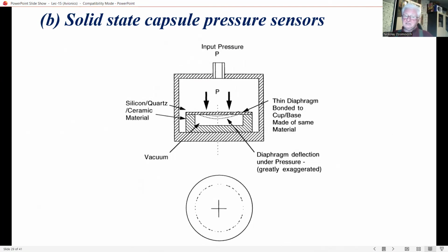Semiconductor technology is used in the fabrication of these sensors and, together with the absence of moving parts, has led to the description as solid state. The technology also enables very small sensors to be fabricated with excellent repeatability because of the semiconductor processes used. The deflection of the solid-state capsule under pressure is typically only 25 up to 50 micrometers for full scale, or even less. The techniques which have been adopted to measure this very small deflection will be described a bit later.